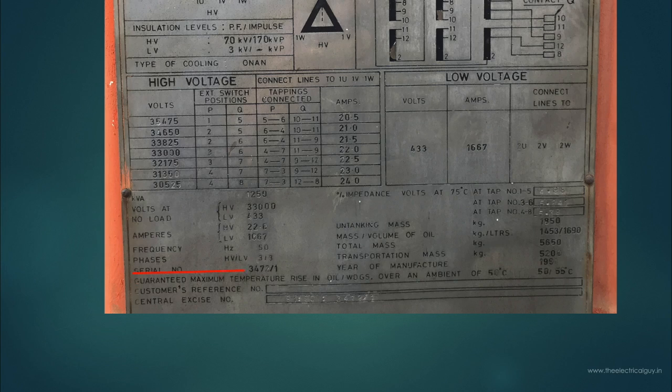Next thing is guaranteed maximum temperature rise in oil or windings over an ambient of 50 degrees. This indicates in case if the ambient temperature goes above 50 degrees then what will be the temperature rise in oil and windings. It is mentioned as 50 or 55 degrees Celsius. So the temperature rise will remain within 50 or 55 degrees Celsius even if the ambient temperature goes above 50 degrees.